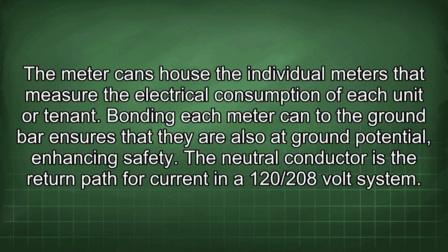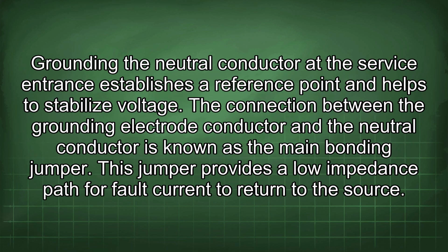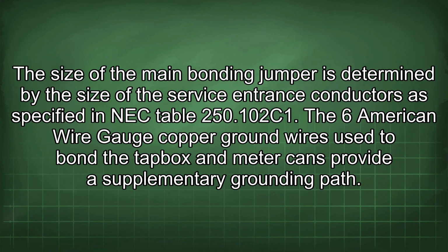The neutral conductor is the return path for current in a 120/208 volt system. Grounding the neutral conductor at the service entrance establishes a reference point and helps to stabilize voltage. The connection between the grounding electrode conductor and the neutral conductor is known as the main bonding jumper. This jumper provides a low impedance path for fault current to return to the source. The size of the main bonding jumper is determined by the size of the service entrance conductors as specified in NEC Table 250.102. The 6 American wire gauge copper ground wires used to bond the tap box and meter cans provide a supplementary grounding path.